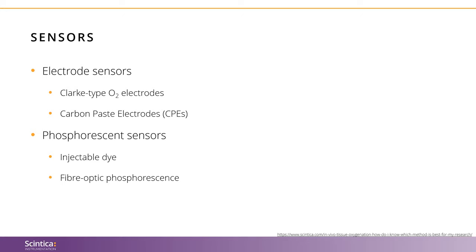Clark-type oxygen electrode sensors are electrochemical sensing instruments where the chemical element of interest — in our case oxygen — passes through a Teflon membrane and chemically interacts with the electrolyte and platinum cathode in the sensor to produce electrons, in other words a current. The current strength is proportional to oxygen in the tissue. These sensors determine the partial pressure of oxygen, but not the absolute concentration.